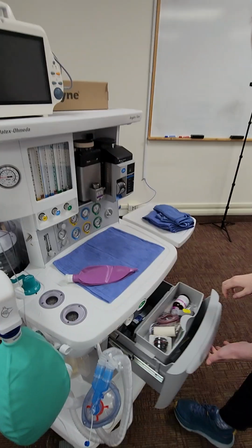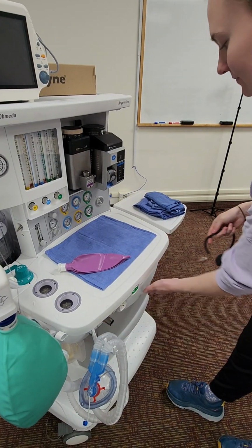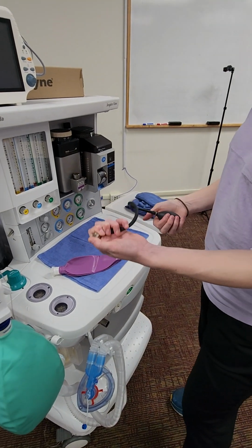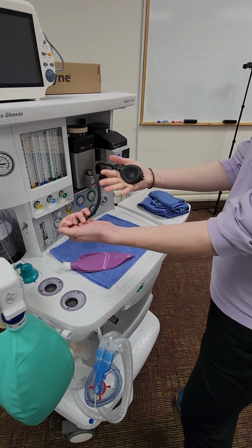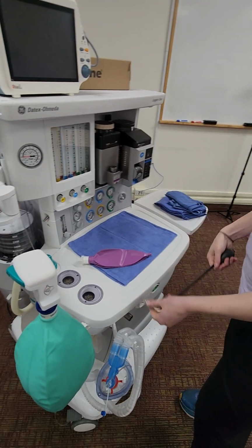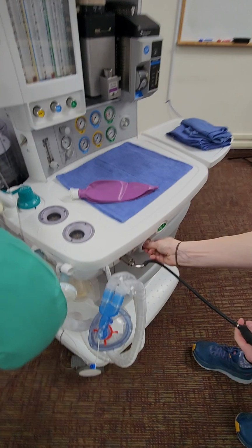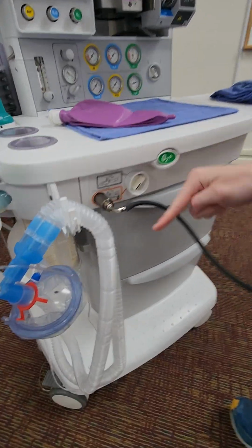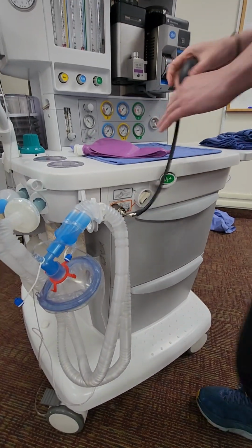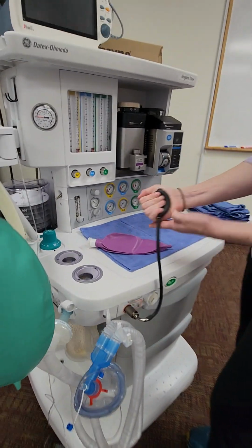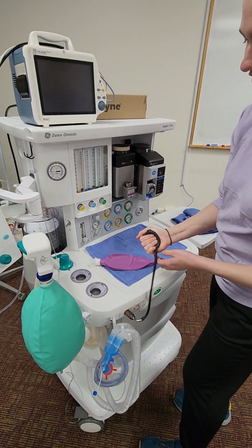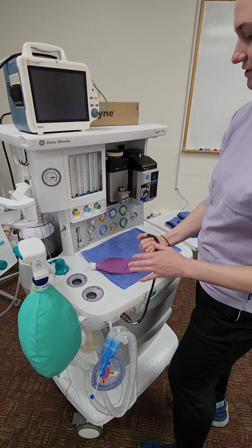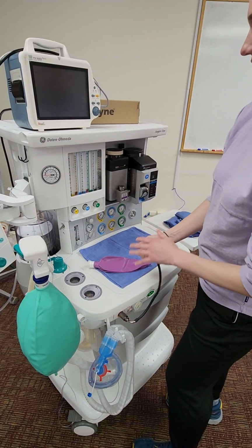So now you're ready for your low pressure system check. This is your bulb. You'll occlude it with your thumb, and then it should stay closed like that. That's how you know there's no issue with your hose. You'll connect it to there. Switch your machine so that it knows to pull from the hose for your low pressure. And then you'll suck all the air out, and this should stay closed for 10 seconds. So if it's closed for 10 seconds, you know you're good to go.